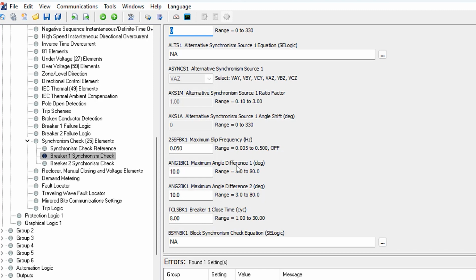Now, in order to do that, of course, we need to know how long the breaker takes to close. That's what this setting is over here. I'm going to leave those two at default. We're allowing a maximum slip frequency of 0.05 hertz. And we're saying that the close time is 8 cycles, which is typical for a breaker. But of course, you need to take a look at the nameplate for your specific breaker and see how long it takes to close, and then enter that setting over here.